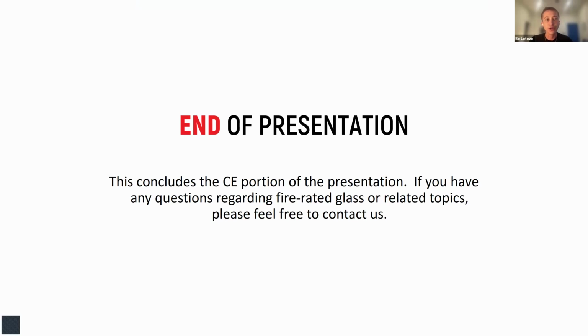All right, let's see. For your first fire-rated glass and doors, this comes as a UL listed system with frame included. What about for fire-rated glass in a wall opening? Does your system require special mullions? Yeah, so anytime you're dealing with a fire resistive solution, that ASTM E119, the glass and the framing have to match. So yes, you need to buy the glass and the framing. It will give you a 1 or 2 hour fire resistive wall together. So yes, the glass and the framing would have the same rating.